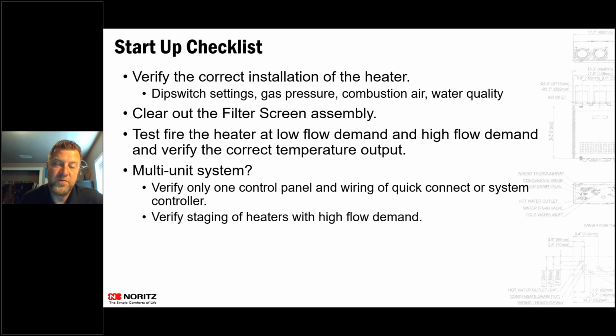If you are working with tankless water heaters, the tools that you really want to have are a gas manometer and a Phillips head screwdriver. Those are pretty much the tools you need to work on a Noritz tankless water heater, because you can take apart everything inside that unit with a Phillips head screwdriver or your hands. Everything is either clips or Phillips head screws. It's pretty sweet. So verify that the dip switches are set correctly, the gas pressure is good, your combustion air is adequate, and that you have something addressing the water quality issue.